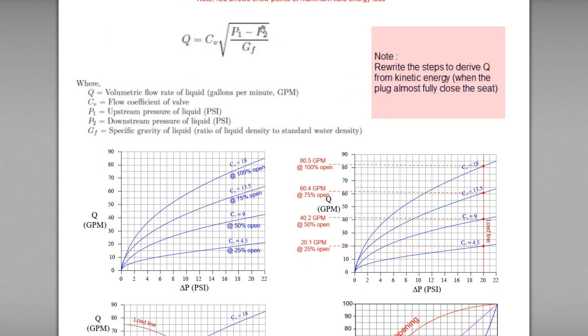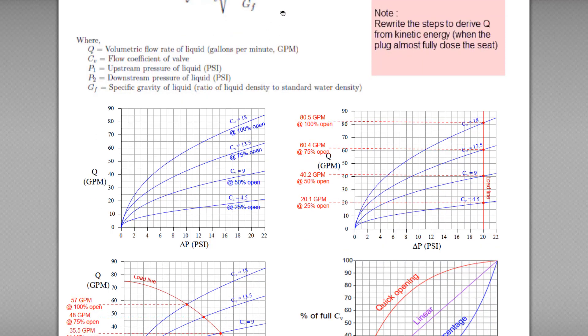We can use this curve to understand the CV further. Let's see, I assume that the differential pressure is fixed. Like in this curve, the differential pressure here is fixed at 20 psi. So from here, you can see the CV reading will change. The CV value change from 4.5 to 9 to 13.5 and 18 depends on the different valve opening position.